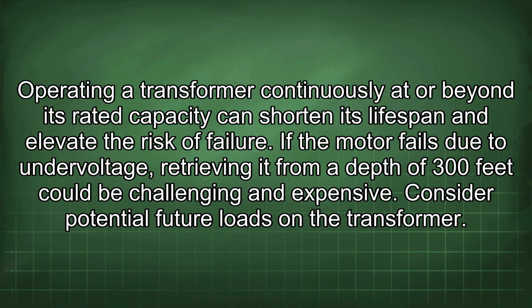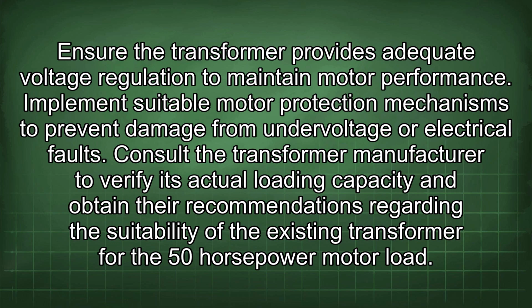Consider potential future loads on the transformer. Ensure the transformer provides adequate voltage regulation to maintain motor performance. Implement suitable motor protection mechanisms to prevent damage from undervoltage or electrical faults. Consult the transformer manufacturer to verify its actual loading capacity and obtain their recommendations regarding the suitability of the existing transformer for the 50 horsepower motor load.